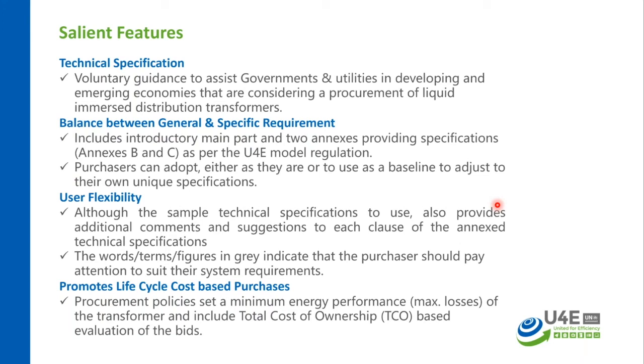This document is essentially one main part and two annexes. The main part is a general guideline which provides all the information related to the technical specification of a transformer, but the two annexes provide the specific information, such as the impedance requirement, the voltage level and the tapping range, etc., for the 50 hertz and the 60 hertz markets. There are Annexure B and Annexure C. Also, this document can be adopted easily and used as the baseline document, and you can make a unique specification by adding additional features to the annexure. This is a very flexible, user-friendly document.